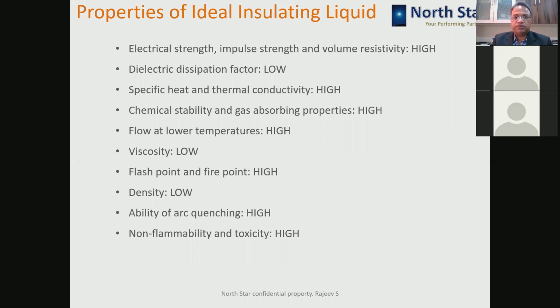So, it should have a high electrical strength, impulse strength, and volume resistivity. Then the dielectric dissipation factor should be low. Then it should be chemically stable. It shouldn't be very volatile or frequently reacting with other things and unstable in nature. It should have excellent gas absorbing properties because transformers generate gases during operation. Then at lower temperature, the flowability should be good.